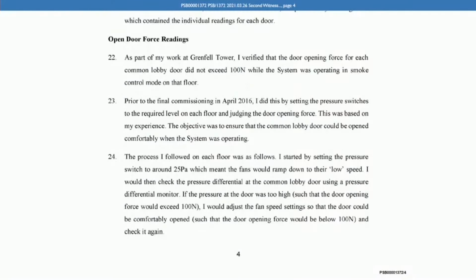Yes, I see. Now, was the system running when you took those readings? On those readings, yes. So it wasn't following the British Standard method? Well, it's both, because you've got to have a differential pressure within the lobby to the stairs, and it's got to be an acceptable level, but that level is derived by the door opening force. The actual levels we were getting varied between about 28 and 33 pascals differential pressure. And the average door opener, if you're interested, was about 12 newtons. It varied. So that's what controlled what pressure we could apply.